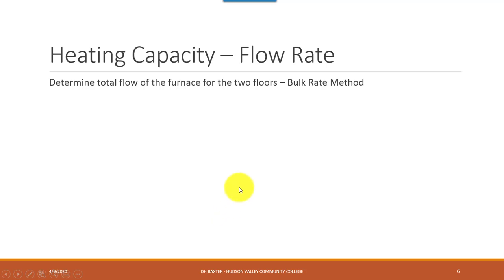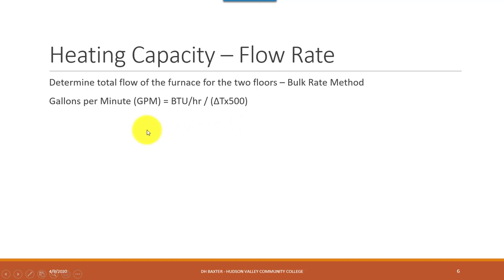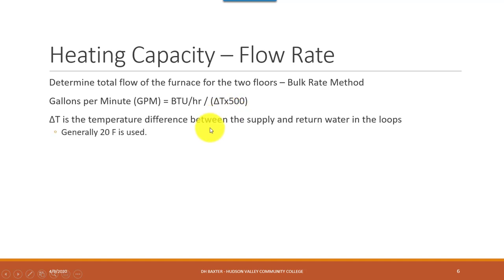So what kind of heat capacity can we expect? There are a couple of ways to determine how big your boiler needs to be, assuming you're going into new construction — not just replacing a boiler that's already there. I'm going to show you the bulk rate method, because this is what most people use. Our gallons per minute required equals BTU hours divided by the temperature change in the loop, times 500. The 500 is a conversion factor to get all the units right. Delta T is the temperature difference between the supply and the return water in the loops.